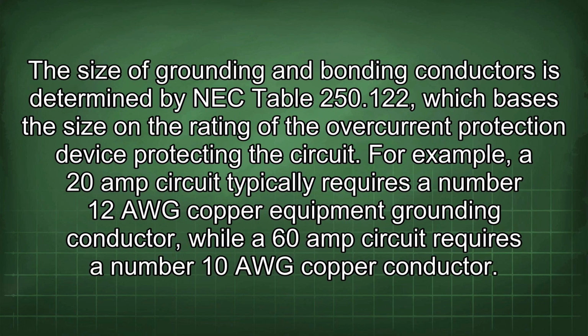The size of grounding and bonding conductors is determined by NEC Table 250.122, which bases the size on the rating of the overcurrent protection device protecting the circuit. For example, a 20 amp circuit typically requires a number 12 AWG copper equipment grounding conductor, while a 60 amp circuit requires a number 10 AWG copper conductor.